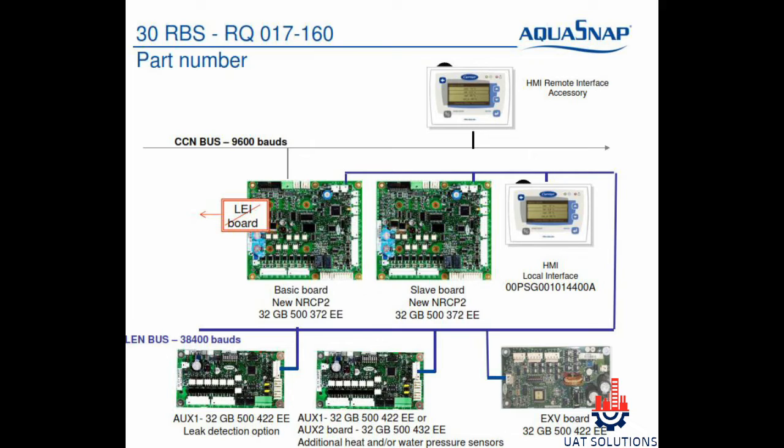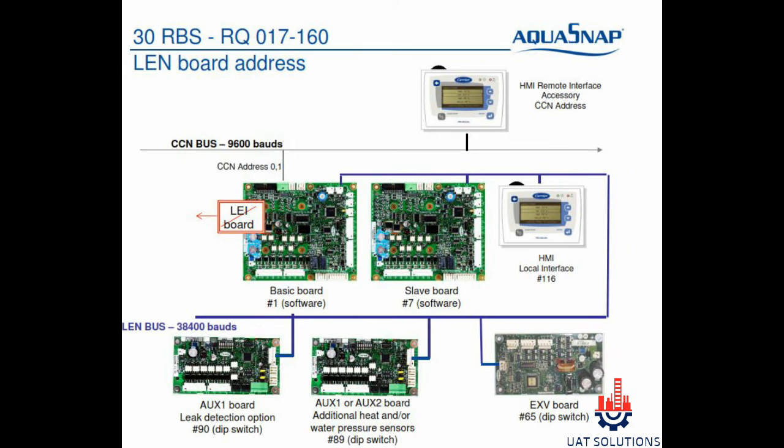Part numbers of all the boards used in Carrier 30RBS and RBQ chiller are as shown. All board addresses are shown. The NRCP2 board and HMI local interface address is set via software, whereas auxiliary boards and expansion valve boards can be addressed using DIP switches.